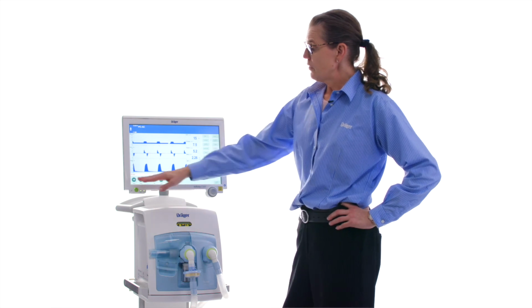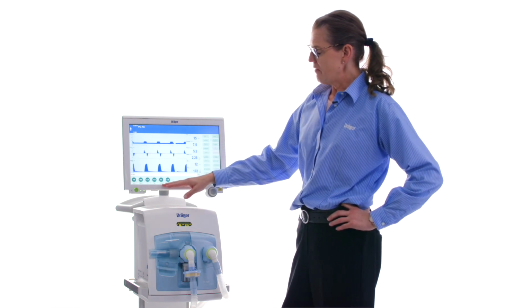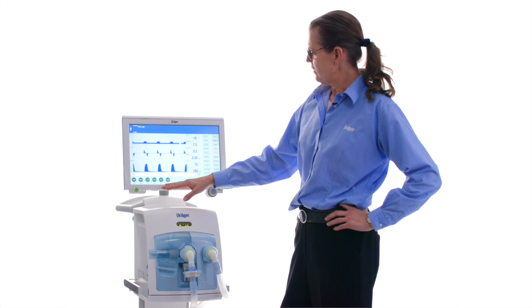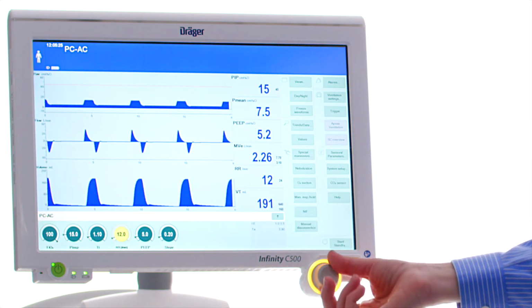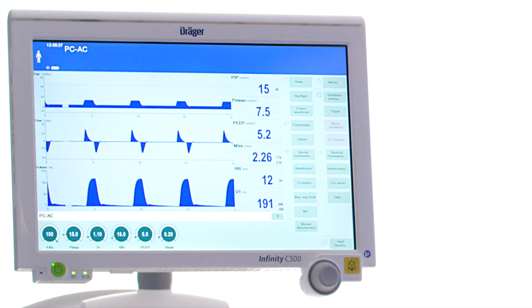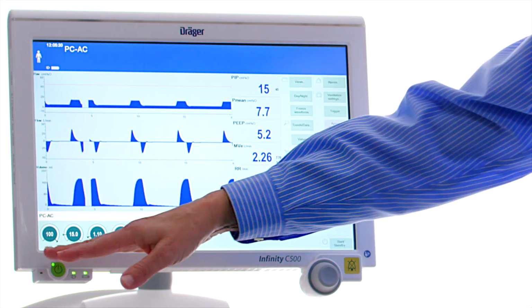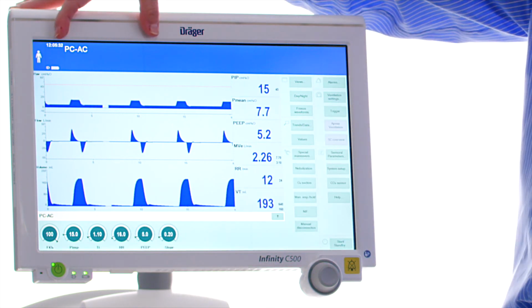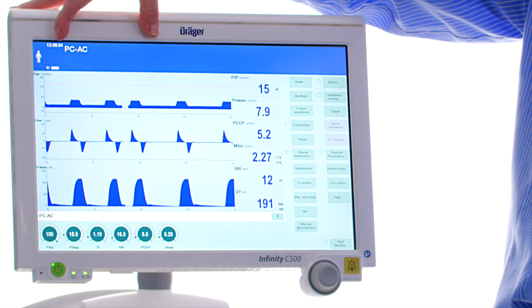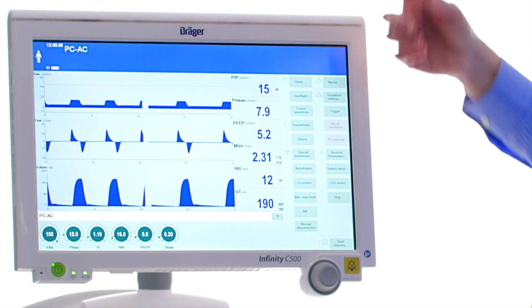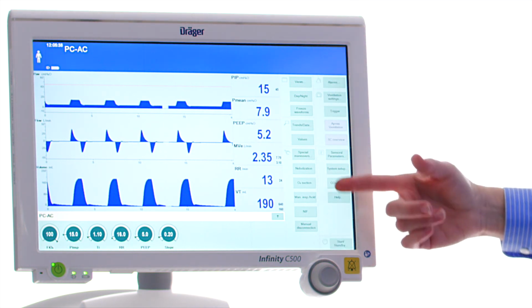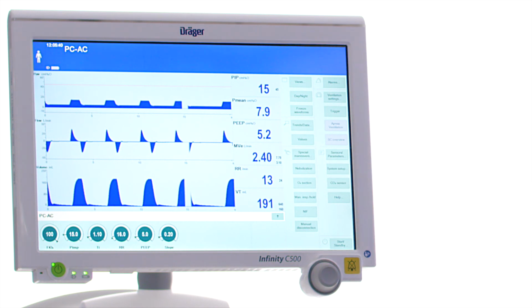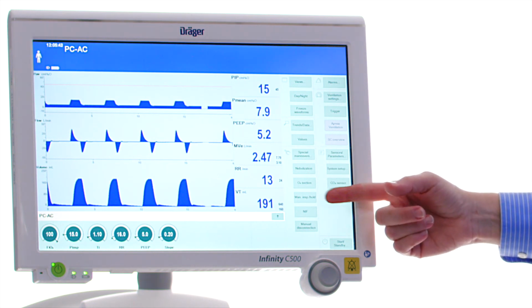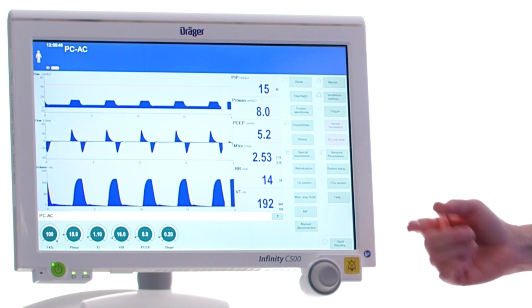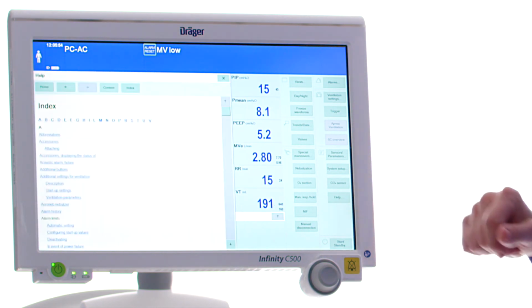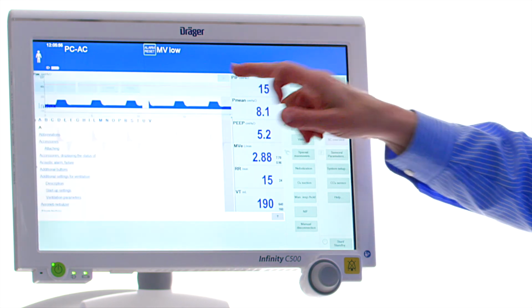So in review, your vent settings sit across the bottom. You have fast access to make changes to your basic ventilation parameters. Touch the button, turn the knob, confirm, touch, turn, confirm. Blue is measured, green is set. Your mode of ventilation and any adjuncts that are active are displayed at the top of the screen, and then you've got shortcut buttons along the side. O2 suction is your 100% for 3 minutes. Manual inspiration is your manual breath button. And Help gives you access to your instructions for use right on the control panel.